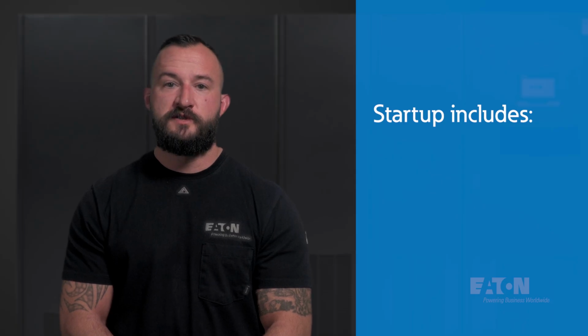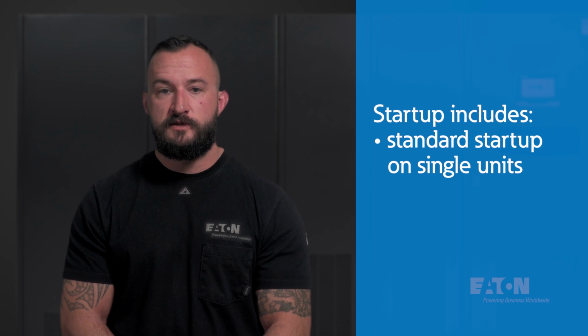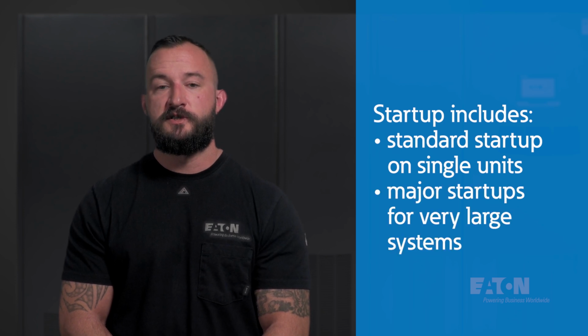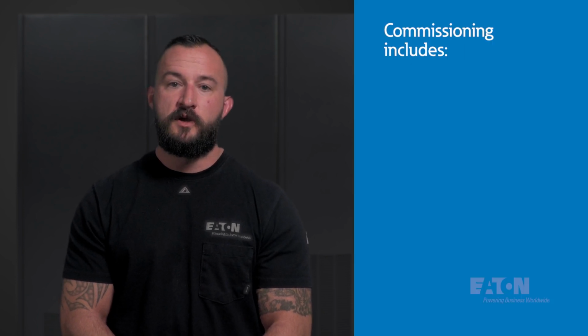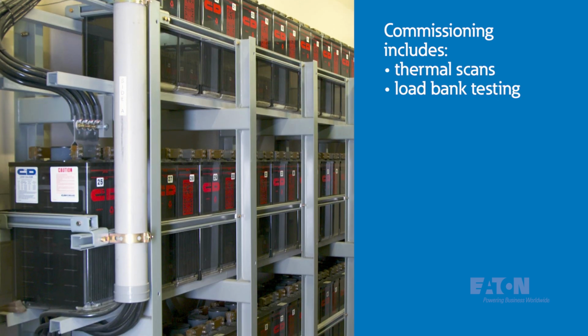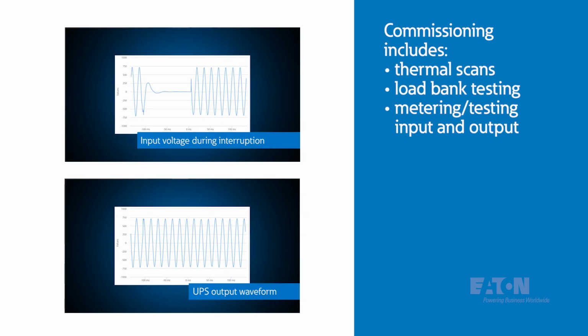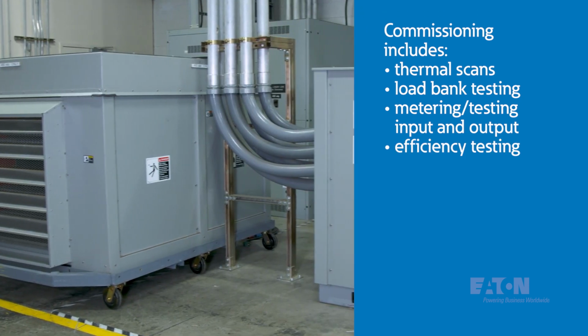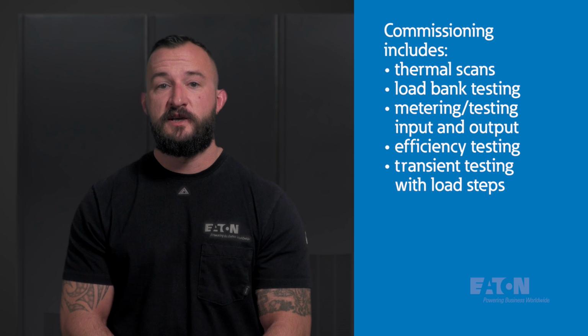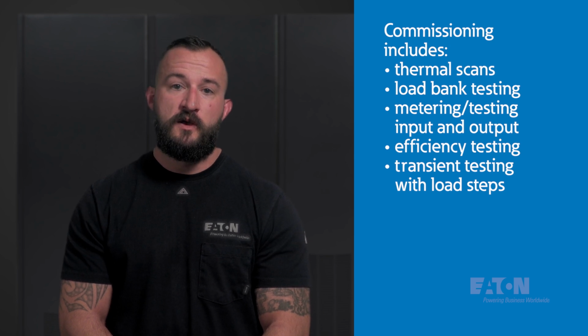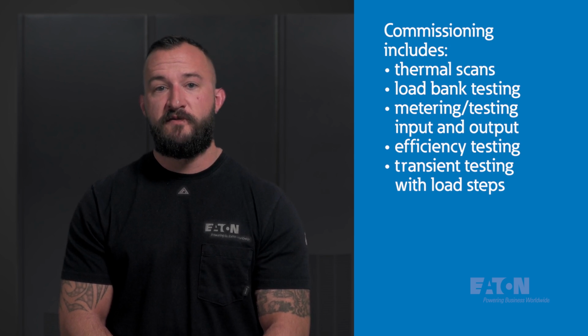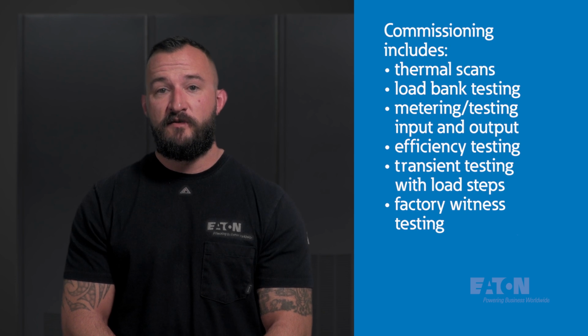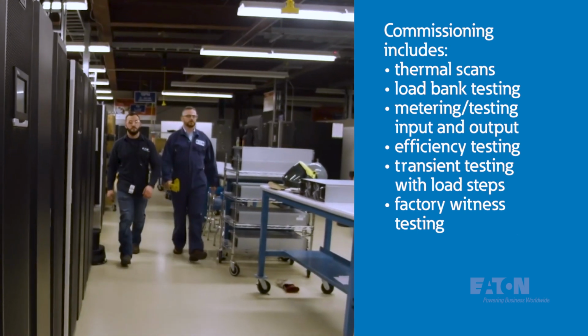The rest of our work includes a similar split between startup, commissioning, modifications, and troubleshooting. Startup would include standard startups on single units and major startups for very large systems. Commissioning would include thermal scans, load bank testing, and metering and testing of the UPS input and output. We also do efficiency testing and verification, as well as transient testing with load steps.